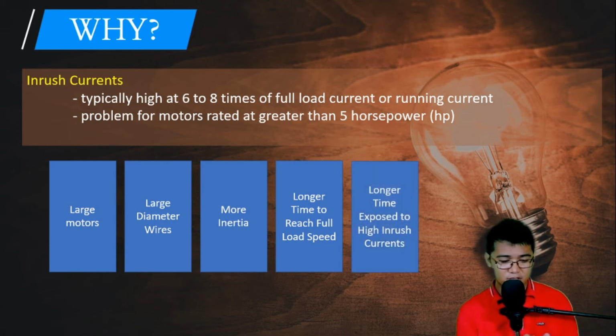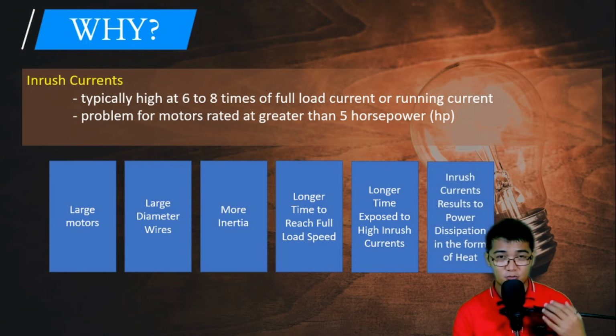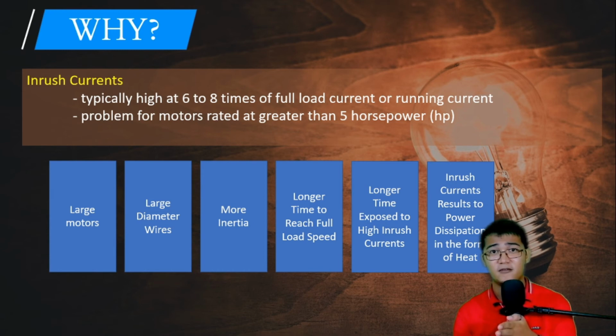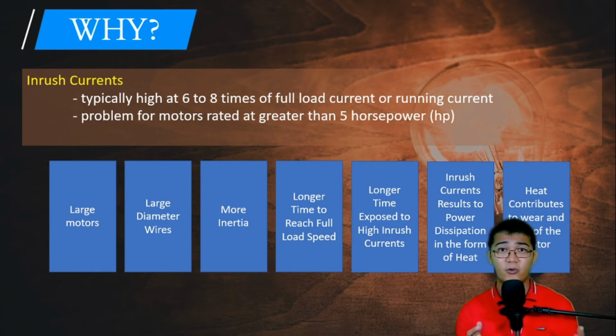And because of this longer time to reach full load speed, there will actually be longer time na expose yung ating motor windings to high inrush currents. Since yung mga coils natin have resistances at may current na dumadaan sa kanya, then it will incur power losses. And we all know that power is the square of the current times the resistance. P is equal to I squared R. Malaki yung kuryente, in-square pa natin times the resistance. So this power dissipation will actually be dissipated as heat, init. And itong init na ito will actually contribute to the wear and tear of our large electric motor. Meaning, mas mapapaikli yung lifespan ng ating motor kapag full line voltage yung gagamitin natin.